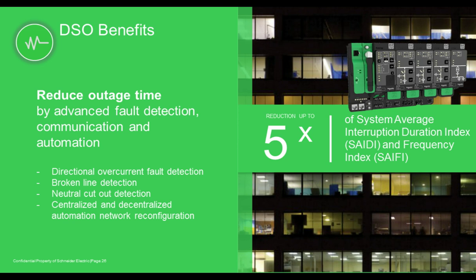This feeder automation solution based on Easergy T300 can clear electrical faults, for example through directional overcurrent detection, broken conductor detection, and neutral cutout detection, closer to where they happen rather than exclusively clearing them at the primary substation, requiring the feeder automation system to be connected to the outage management center to communicate that a fault has occurred.